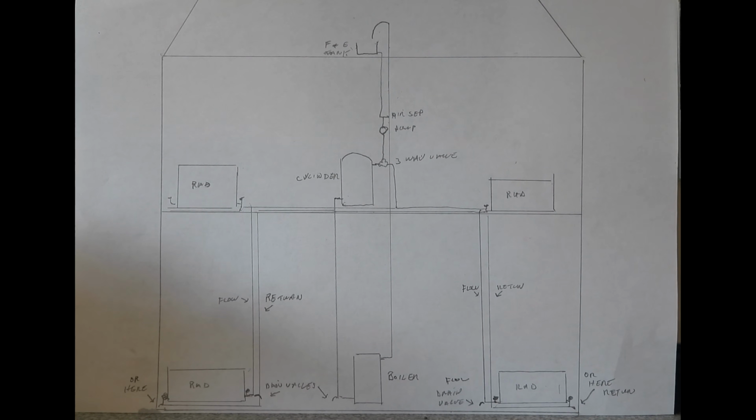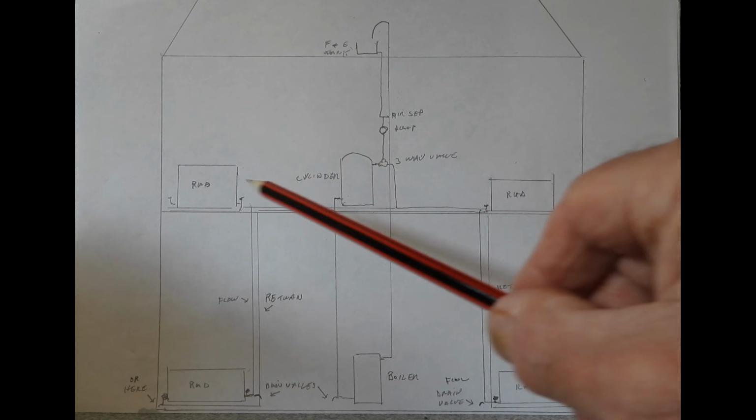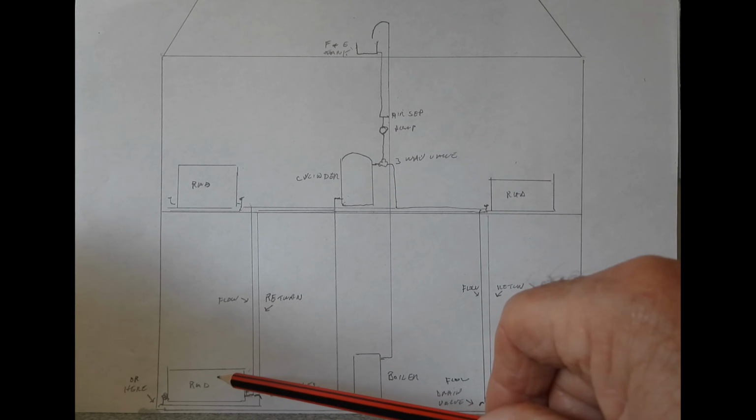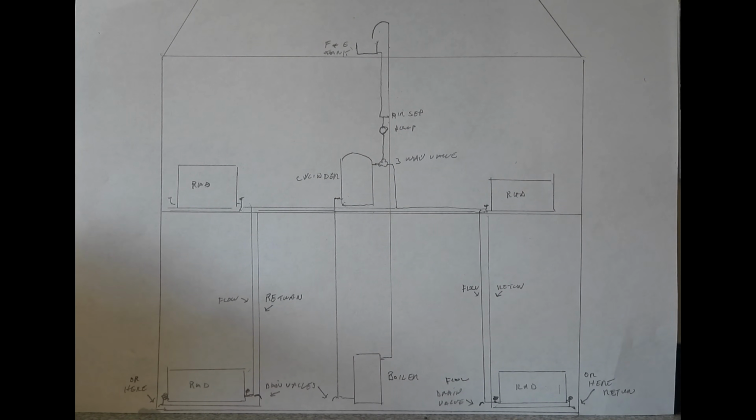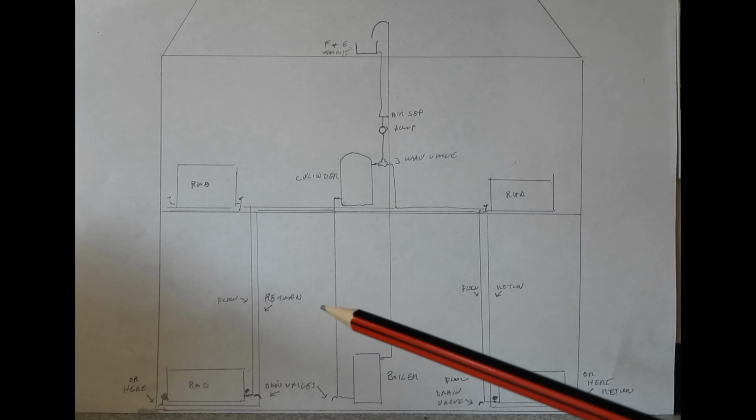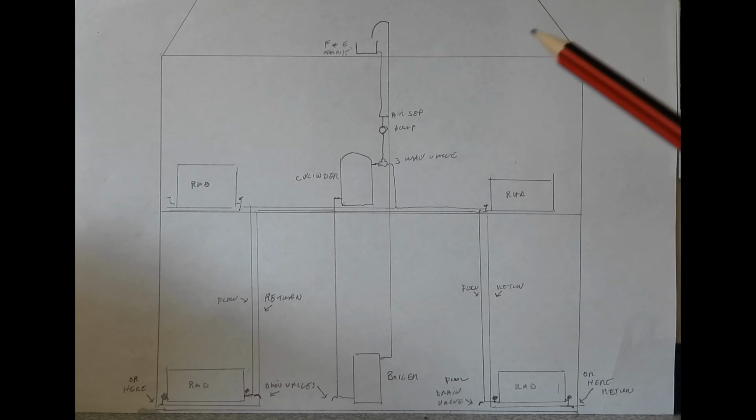And that's why you'll quite often see drain valves, it may be on the flow or the return, it's the same there, and whichever one they're on, it doesn't matter, you've got to drain it out from there. So if you thought to yourself, well, I want to drain the system out to put inhibitor in, then you thought just put a drain valve hose on that one on the boiler, which is quite often where they are, you'll only empty that bit and the upstairs radiators. This rad and this side would remain full up. So you've got to go independently to each drain valve, doesn't matter which end, and empty them. So you've got to do a longer job.